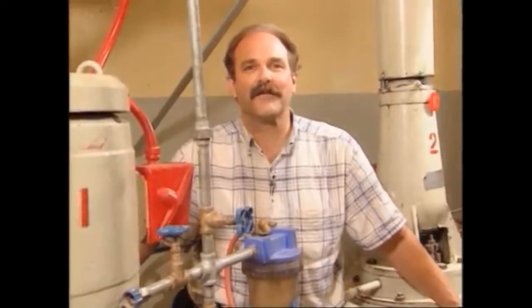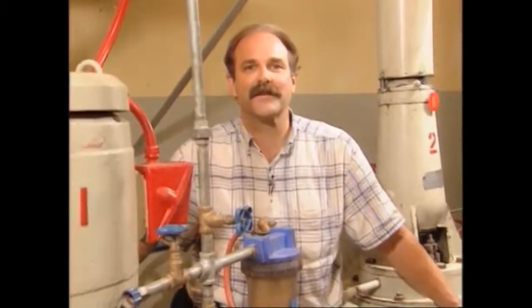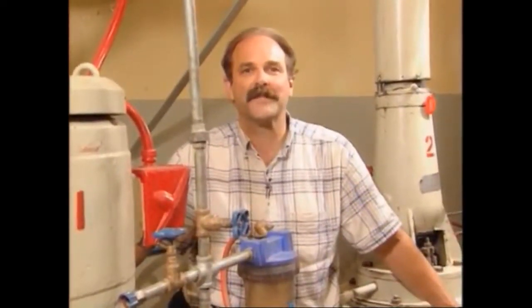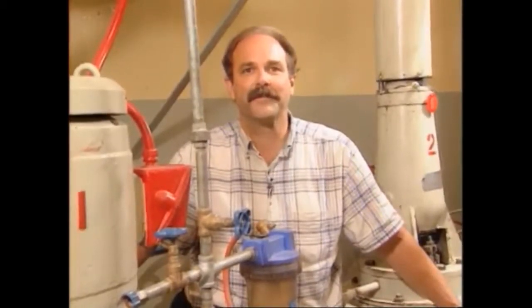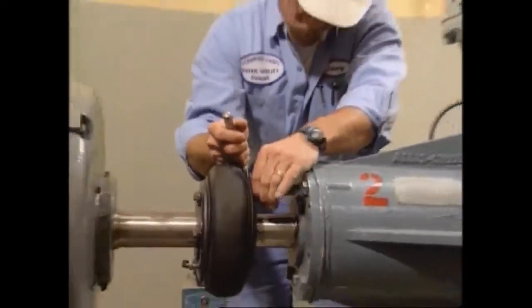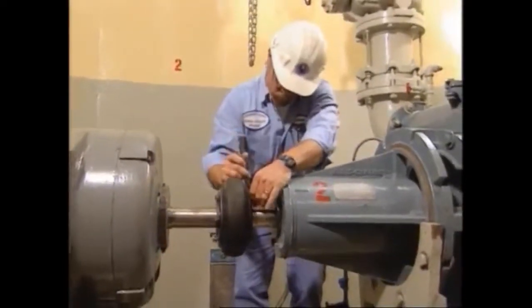Whenever two pieces of rotating equipment are used, such as a motor and a pump, there must be some means of transferring this torque from the motor to the pump. Couplings are designed to do this. To function as intended, the equipment must be properly aligned at the couplings.